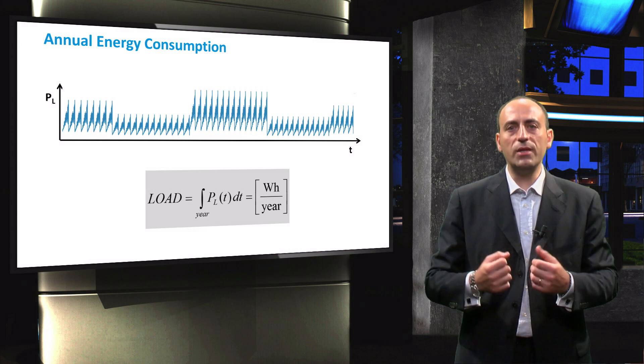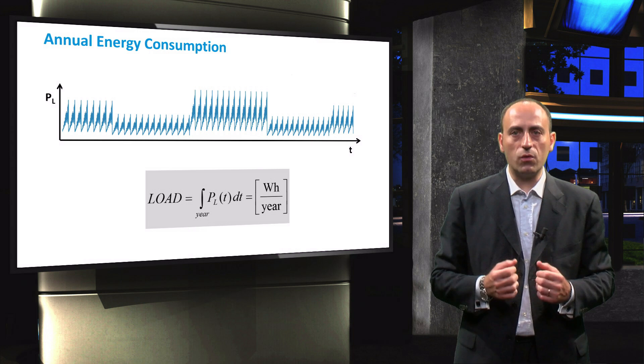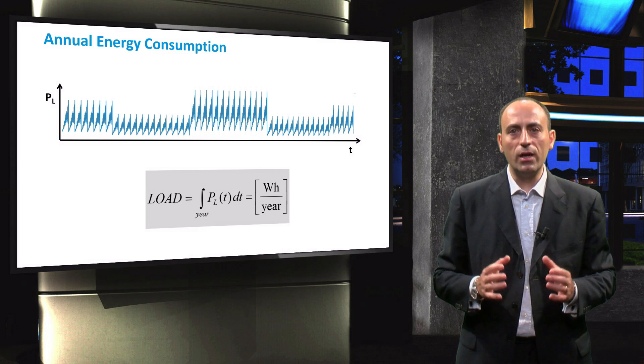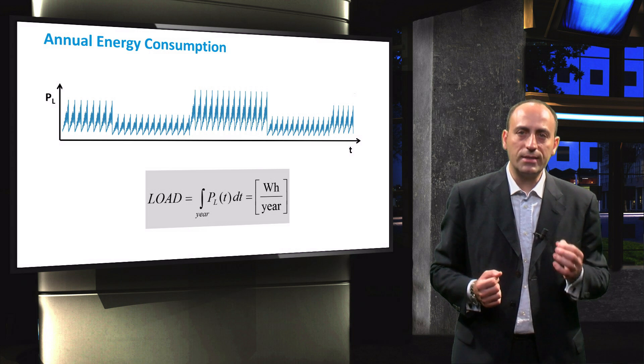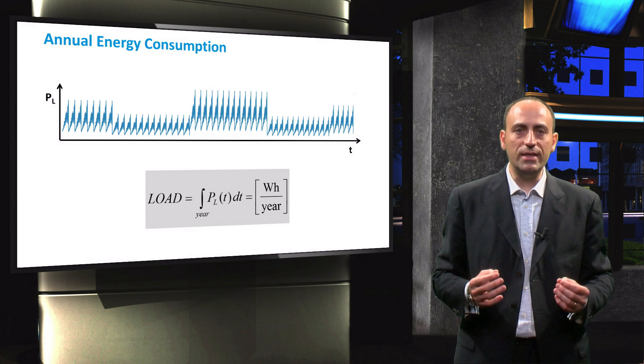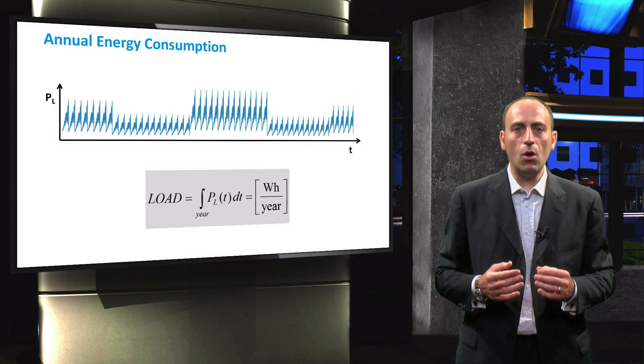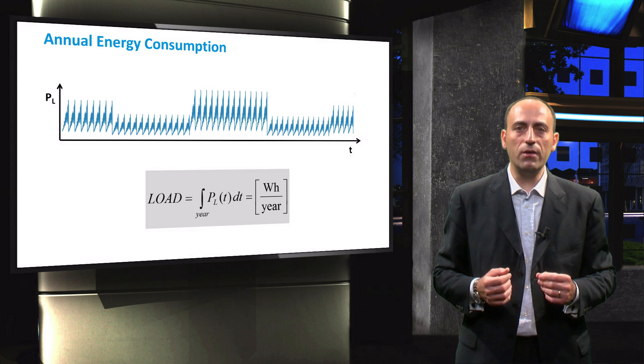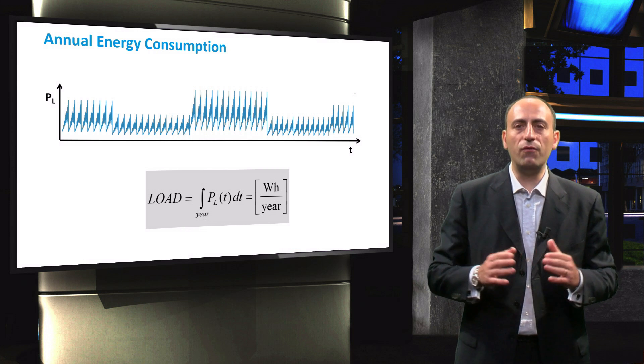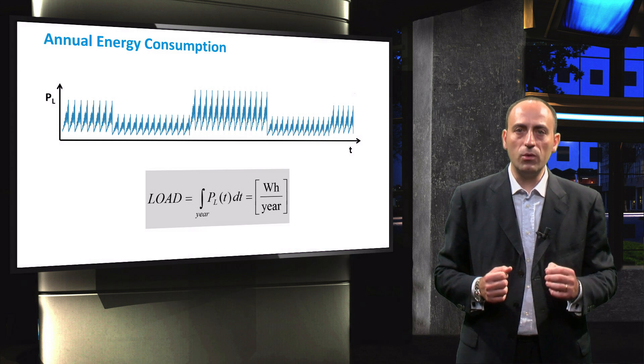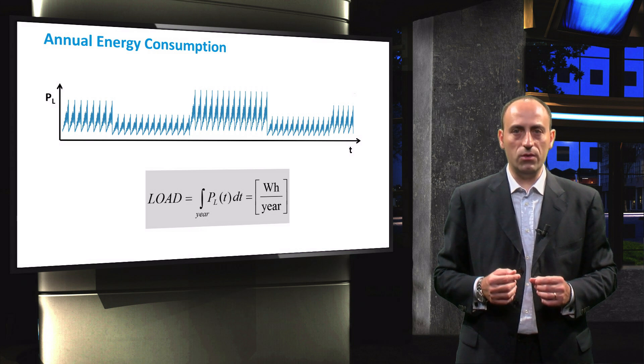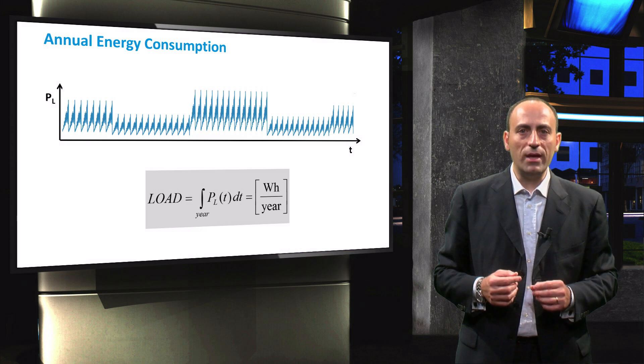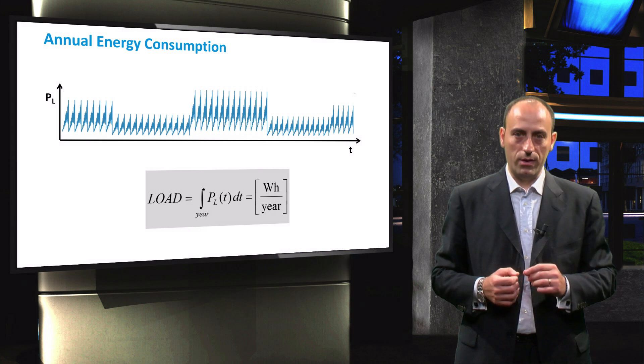After obtaining a load profile of all the loads connected to a PV system, the total energy demand over a period of time can be determined. It is calculated by integrating the instantaneous power of the loads over the considered time period. The equation shown here considers the load demand of a full year. This is an important parameter in PV system design, which will be used again in other videos. The total load demand is expressed in watt-hour per year.